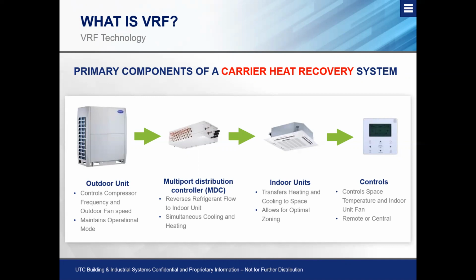But the heat pump system, of course, has two pipes as well. The only difference between the heat pump system would be the fact that it does not have an MDC, a branch box, a flow selector, whatever you want to call it. It does not have that item that allows, that's not an MDC. Okay, so when you look at the carrier system, the heat exchange process for the heat recovery happens within that multi-port distribution controller, separated into three different states of refrigerant: hot gas, liquid, and suction.